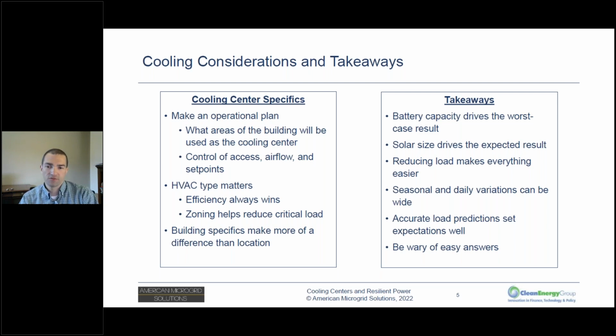Airflow specific to your HVAC system and how you control where your air handling units are pushing that conditioned air. And then set points—you might decide that as a cooling center, when connected to the grid, you'll keep the room at 70 degrees in the summer. You might also want to conserve energy and keep the system operating when off-grid, so if the power goes out, you reset those set points to 80 degrees. It's still more comfortable than outside, but you're using a third less energy than you would have otherwise.